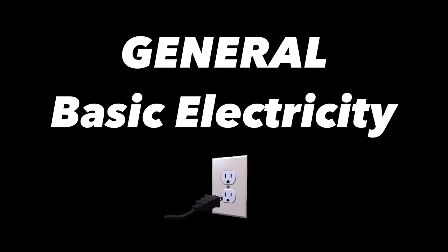What is used to neutralize spilled electrolyte from a lead-acid battery? A solution of bicarbonate of soda and water. How high should an electrolyte level be in a properly serviced lead-acid battery? Only up to the level of the indicator in the cell.